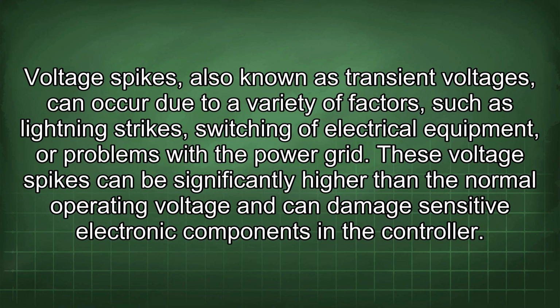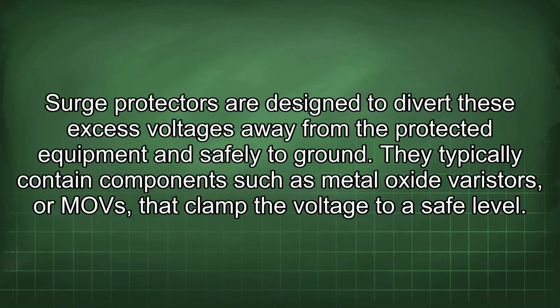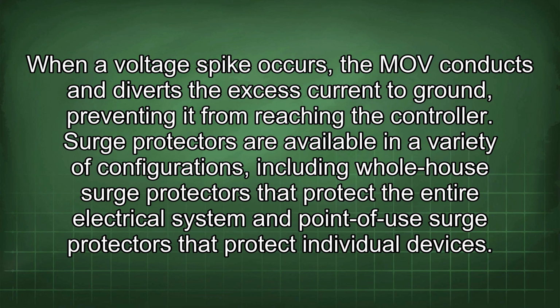These voltage spikes can be significantly higher than the normal operating voltage and can damage sensitive electronic components in the controller. Surge protectors are designed to divert these excess voltages away from the protected equipment and safely to ground. They typically contain components such as metal oxide varistors, or MOVs, that clamp the voltage to a safe level. When a voltage spike occurs, the MOV conducts and diverts the excess current to ground, preventing it from reaching the controller. Surge protectors are available in a variety of configurations, including whole house surge protectors that protect the entire electrical system and point-of-use surge protectors that protect individual devices.